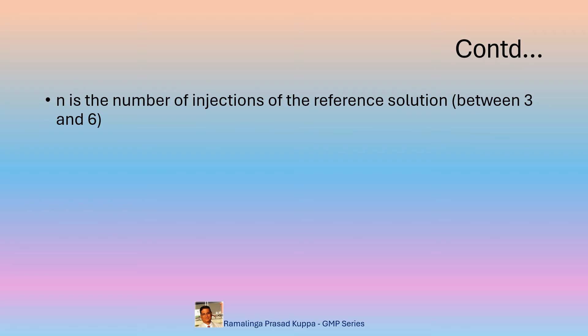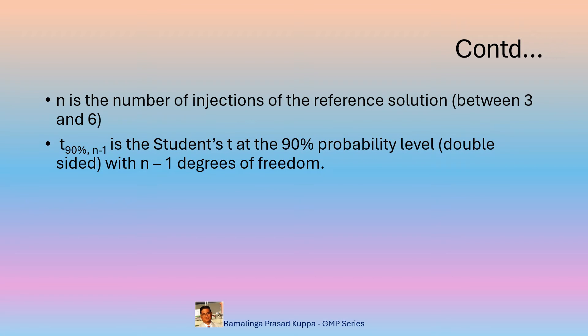N is the number of replicate injections. The minimum requirement is 3 and the maximum is 6. T90% N−1 is the Student's T at the 90% probability level, double-sided, with N−1 degrees of freedom. These are statistically derived figures obtainable from the internet; however, the table is provided in the next slide for reference. Remember that the T90 values should be taken for N−1 degrees of freedom. That means for 3 injections, the T90 value for 3−1 = 2 degrees of freedom should be considered. Similarly, for 4 injections it should be 3, for 5 injections the value of 4, and for 6 injections the value of 5 should be considered.